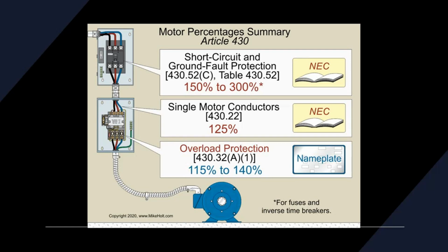The code book tells us that when we are looking for short circuit and ground fault protection, meaning the breaker in most cases, or fuse, that is our short circuit and ground fault protection, it is sized in the NEC under these two tables, 430.52 C, 430.52. Table 430.52 will tell us that we can actually upsize that breaker by 150% to 300%.